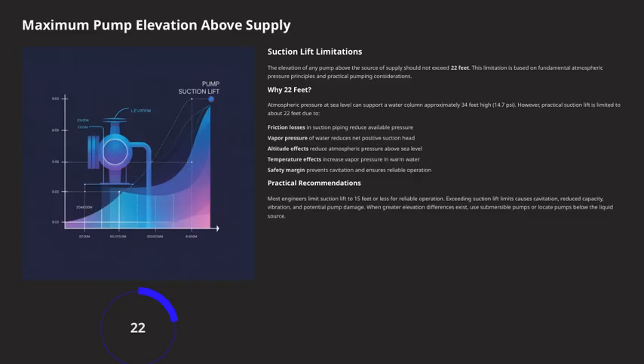Let's talk about the maximum pump elevation above the supply source. The key point here is that we generally shouldn't place a pump more than 22 feet above the supply. This limit is rooted in fundamental atmospheric pressure principles and practical pumping considerations. Now you might wonder why 22 feet specifically. Well, at sea level, atmospheric pressure can support a water column of about 34 feet, given the standard 14.7 psi. But in real-world applications, the practical suction lift is limited to around 22 feet.